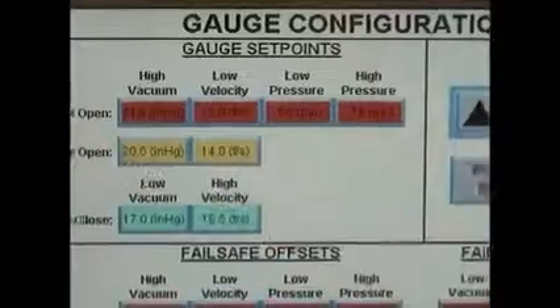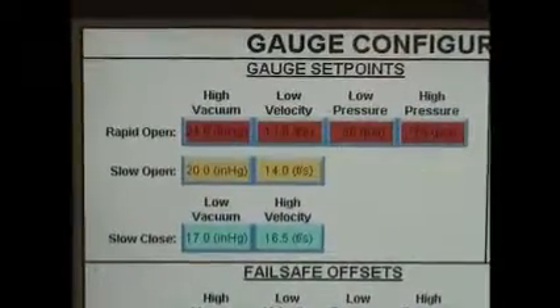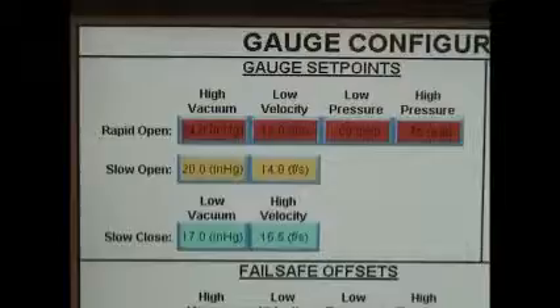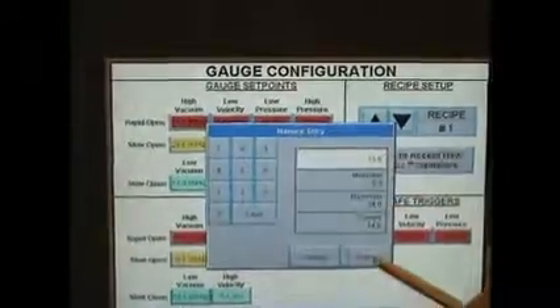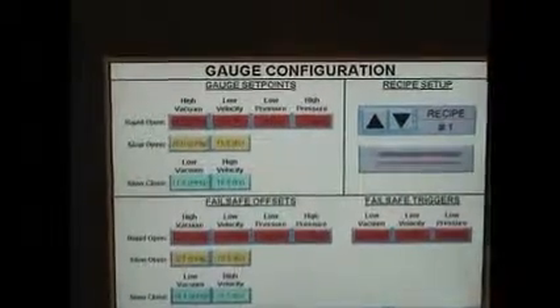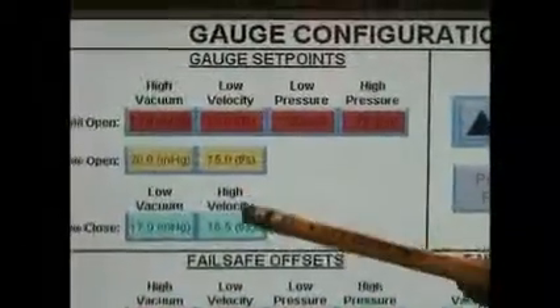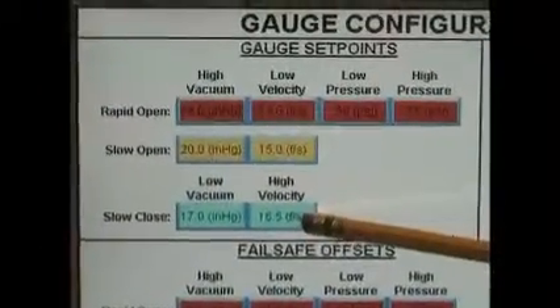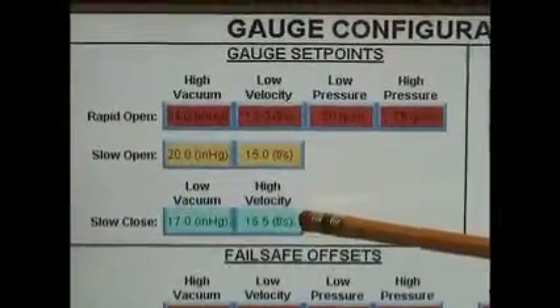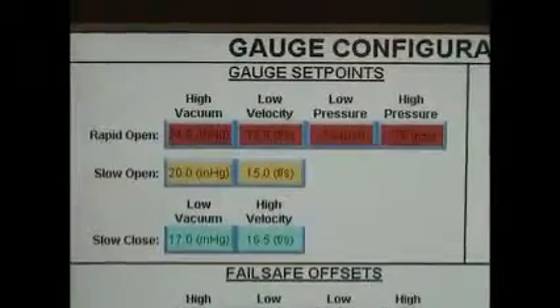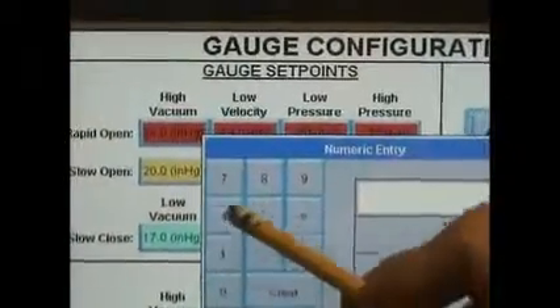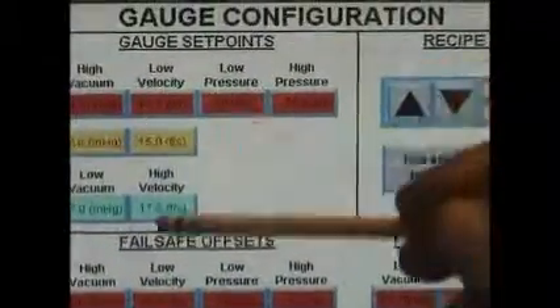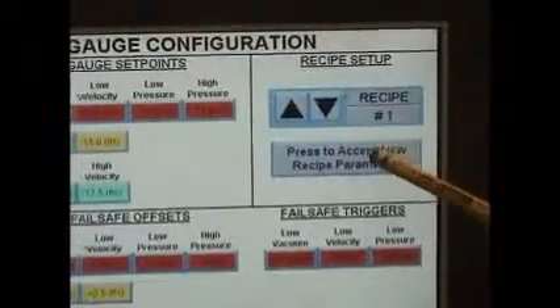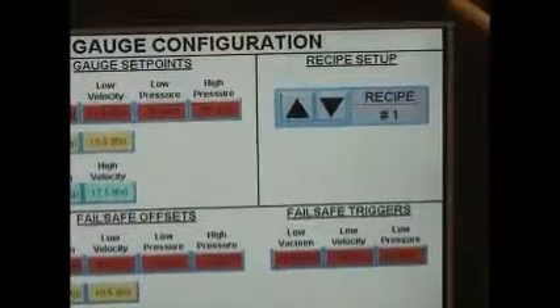The next is our slow open. This is where the valve is going to start to step itself open. Currently we're set at 14. Let's change that to 15. Let's say we want the valve to start opening a little quicker at 15. And then the area where our green zone and our turquoise zones meet is this area right here. We're going to change that to 17.5, for example. Hit enter. Since we made this change, we're on recipe number 1. We're going to touch or press to accept new recipe.